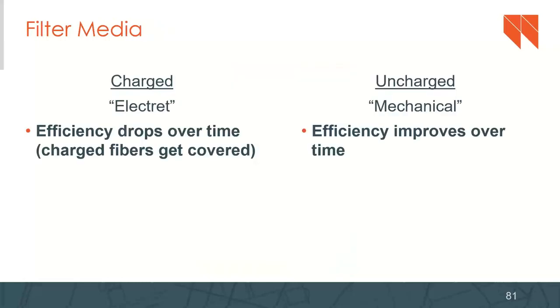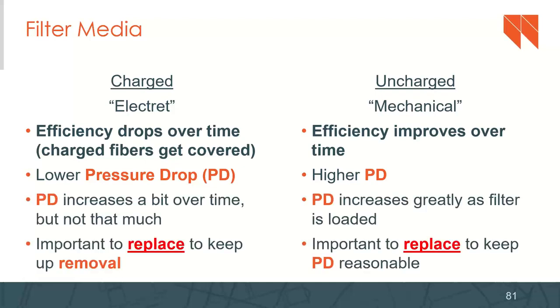These different kinds of pleated filters can come in charged or uncharged. So with a charged or electret filter, you can have a lower pressure drop. If it is an uncharged filter, you have a higher pressure drop. So as the air moves across the filter, the pressure is going to drop more in the uncharged filter than the charged one.